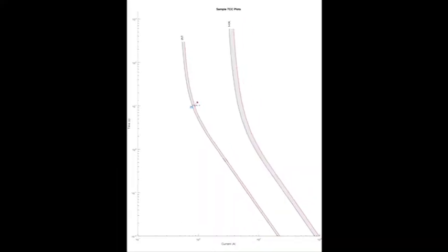Answering another question, we could say, if our 25T speed fuse were to experience a fault of, bad example, let's say 500 amps. If a 25T fuse were to experience a fault of 500 amps, how long would it take to operate?